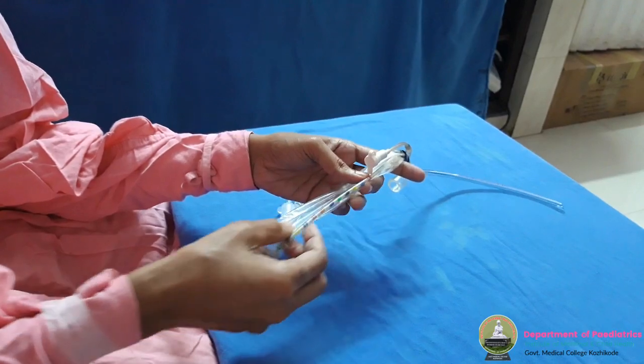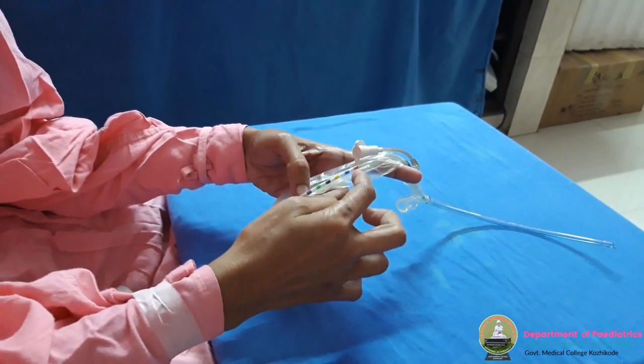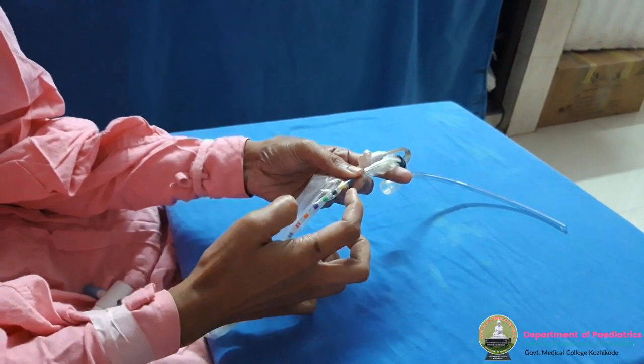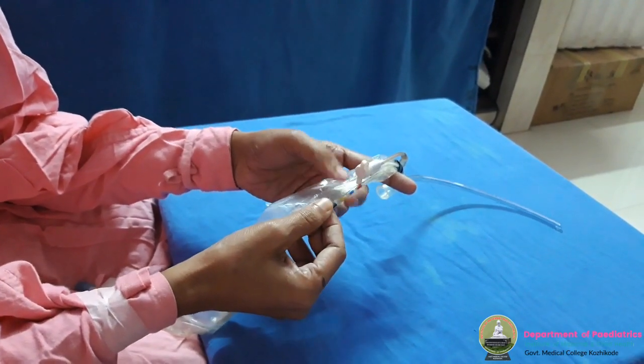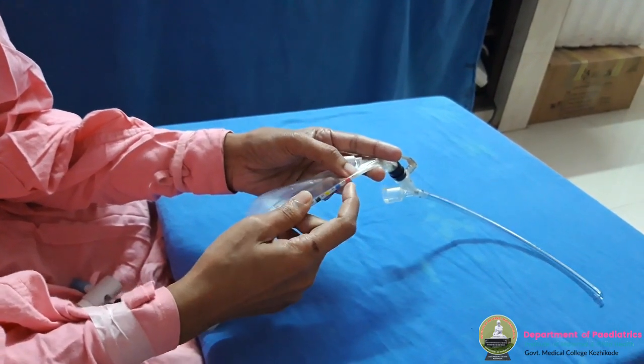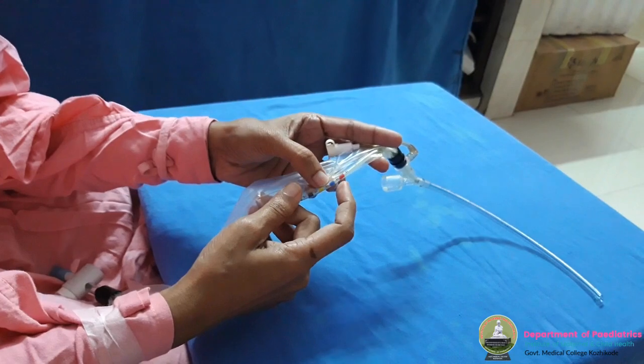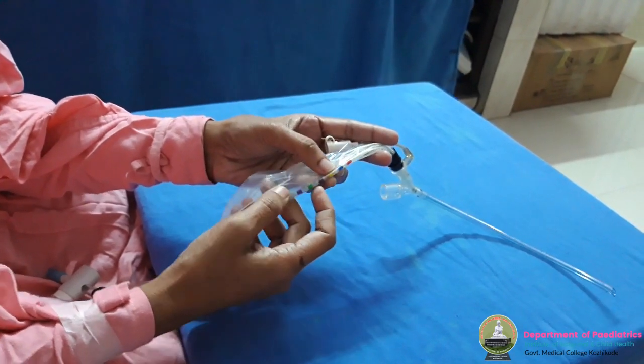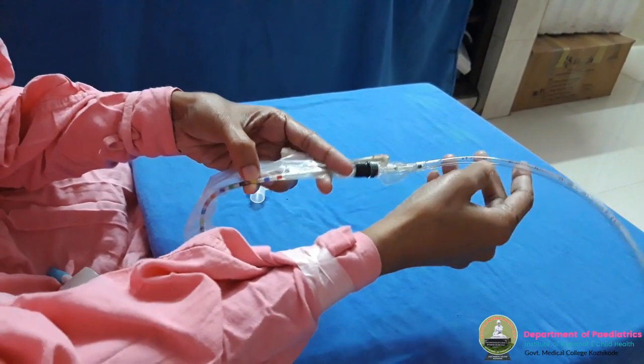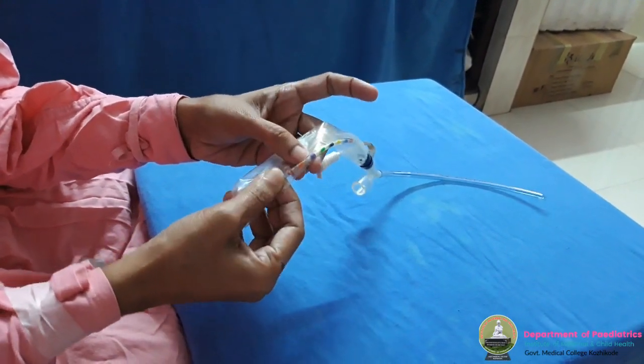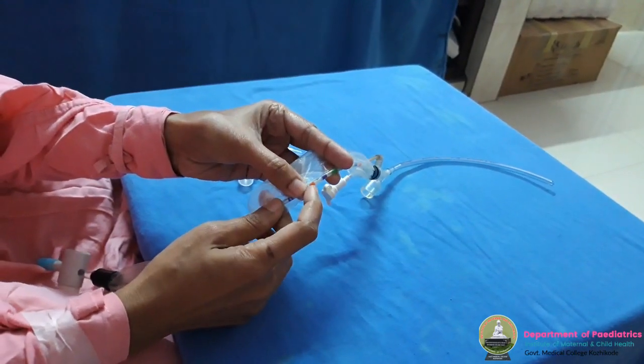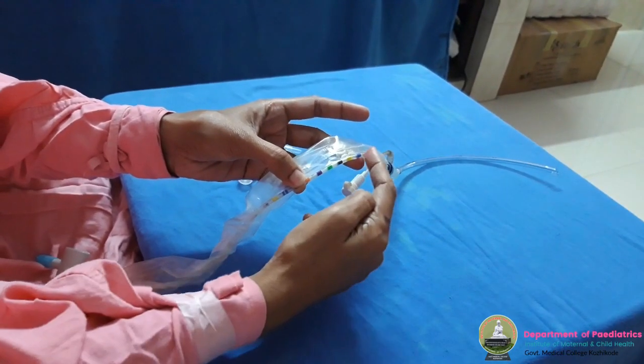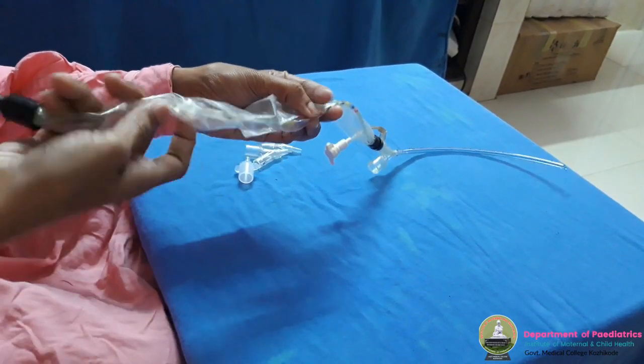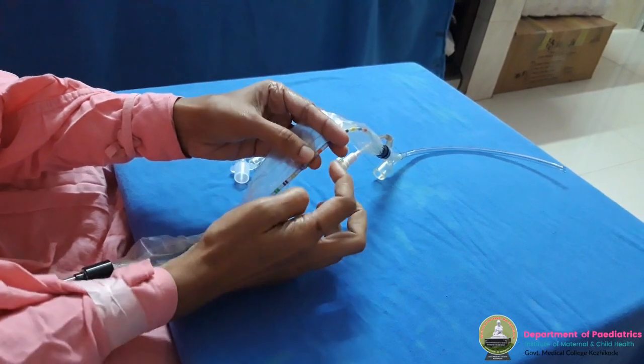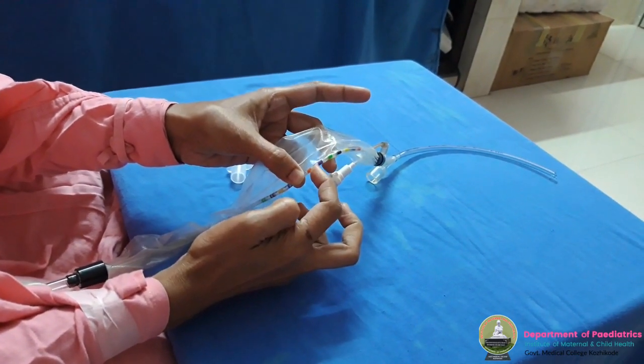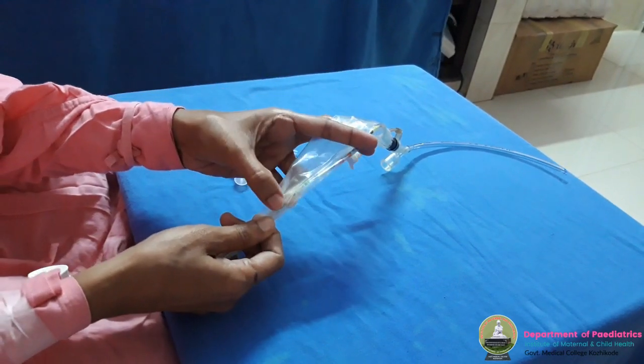In the catheter of the closed suction device there are also centimeter markings with numbers and color codes. Through this polythene cover you can see the number and the corresponding color code. For example, 12 is red, 13 is blue, 14 is yellow, like that. Here it is 18, so we have to see which color corresponds to 18. This is 18, this orange band. Remember, these colors are repeated at the distal end also, but as double bands. So a single orange band corresponds to 18 centimeter. It is not a double band orange; that may be some other centimeter.